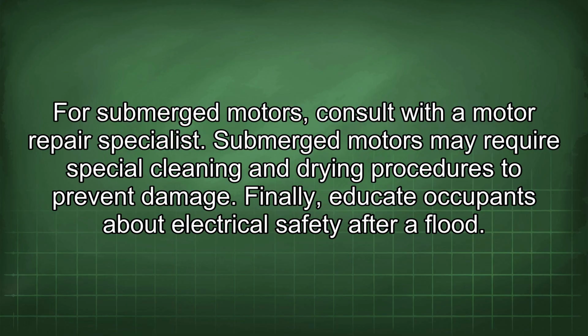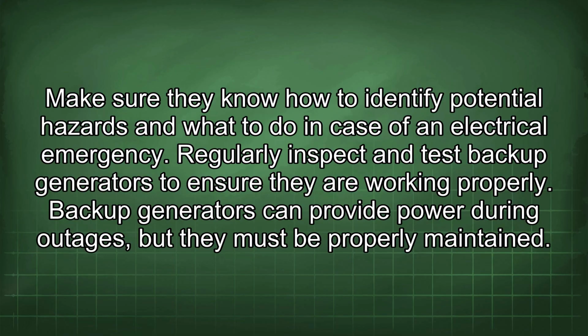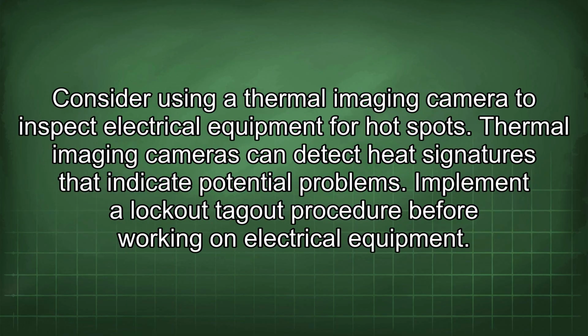Finally, educate occupants about electrical safety after a flood. Make sure they know how to identify potential hazards and what to do in case of an electrical emergency. Regularly inspect and test backup generators to ensure they are working properly. Backup generators can provide power during outages, but they must be properly maintained. Consider using a thermal imaging camera to inspect electrical equipment for hotspots. Thermal imaging cameras can detect heat signatures that indicate potential problems.